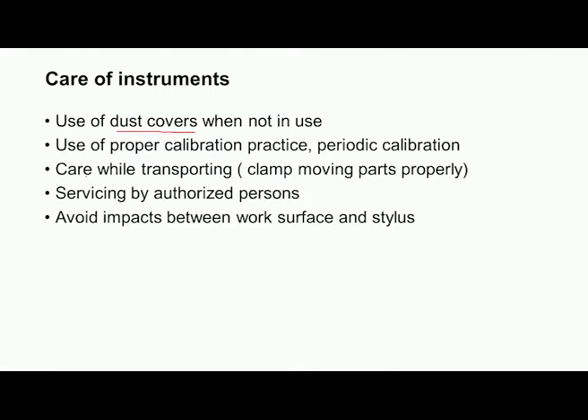And whenever we transport the instrument from one place to another, it should be packed properly. All the moving parts should be properly clamped. We should follow the instructions given by the manufacturer of the instrument, and as per the instructions we should properly clamp them. If the moving parts are not clamped, then during transit they may move in and out, and because of that they may get bent, so they become useless. To avoid such things, proper care should be taken while transporting the instruments. And servicing of the instrument should always be carried out by authorized persons. Unauthorized persons should not be allowed to do the servicing of the instruments.